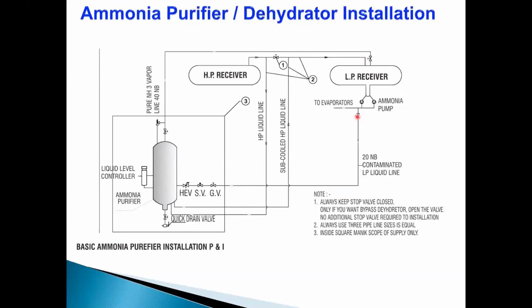We tap low temperature liquid from the LP vessel or the evaporator, and when it comes here, any ammonia will get evaporated because of the temperature of the coil. The gas will go back into the system, and whatever water, oil, or dirt is there will accumulate at the bottom. Initially, all this part will be covered with frosting when it is ammonia, and when water starts accumulating, the frosting will go and you can drain the liquid from the bottom valve.